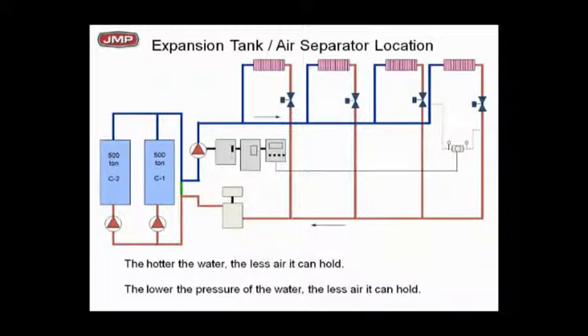It will work at many different locations, no doubt. But we believe where we got it shown here, this is what Bell and Gossett preaches: put it on the return from the secondary loop. That's where you're going to have the hottest water and the lowest pressure right there because it's close to the common.